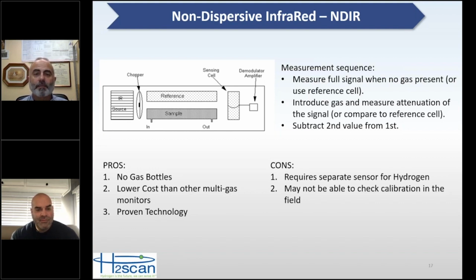There are monitors on the market that are using this technology. The accuracy of this technology has improved a lot over the last 10 years, and so these are becoming more and more popular. So there are pros. There are no gas bottles. They're generally, I believe, lower cost than other gas monitors, depending on the design, and it is a proven technology. The cons are it does still require a separate sensor for hydrogen. I'm not sure about oxygen on this one. I believe if it has oxygen, you also need a separate sensor for that. And I'm not sure if you can check the calibration in the field. I don't believe so, but maybe somebody can educate me on that in the future.